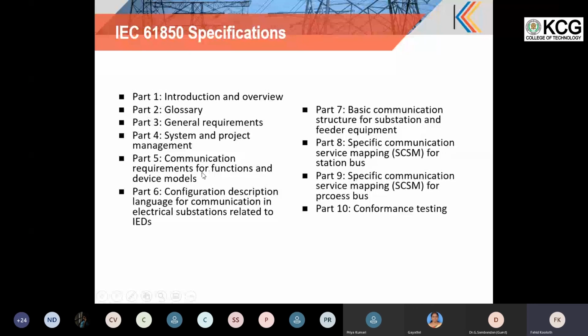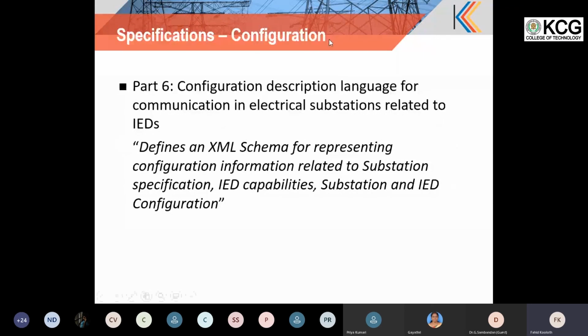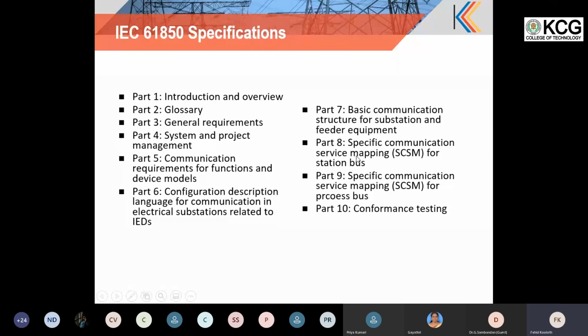Then part 6 deals with the substation configuration language, that is the XML schema and other details, of which I gave a brief overview in the last part. Then part 7 deals with the abstract communication interface, data models, logical nodes and other details. Once that abstract communication service interface is defined, the specific communication service mapping to MMS is defined in part 8, and GOOSE is also defined in part 8. Part 9 defines the sampled value transmission, and part 10 defines conformance testing, which I have mentioned, that is the GOOSE timing requirement and how we measure it. So these are the specification standards.